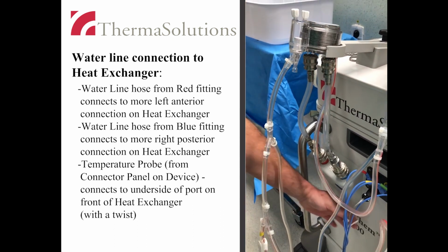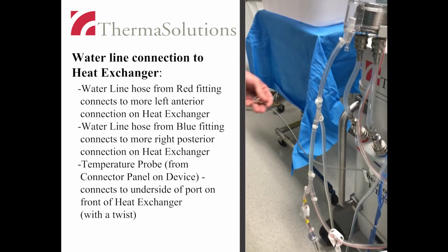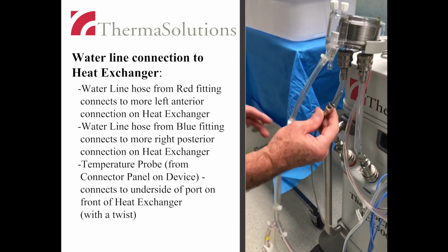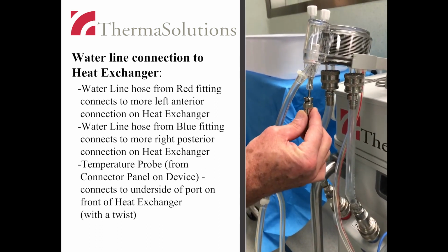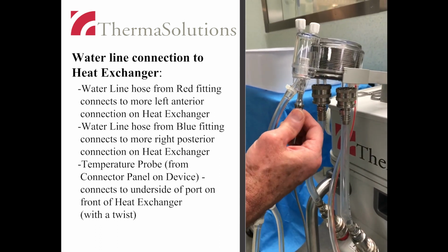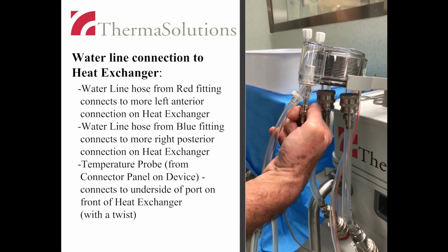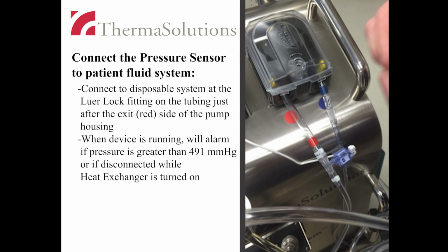The gray temperature probe from the connector panel on the device connects to the anterior port of the front of the underside of the heat exchanger. Insert the pin on the probe and twist to secure. Connect the pressure sensor to the disposable tubing system. The connection point is at the luer lock fitting located on the tubing on the exit side of the pump. This is the left side of the pump with the red dot.